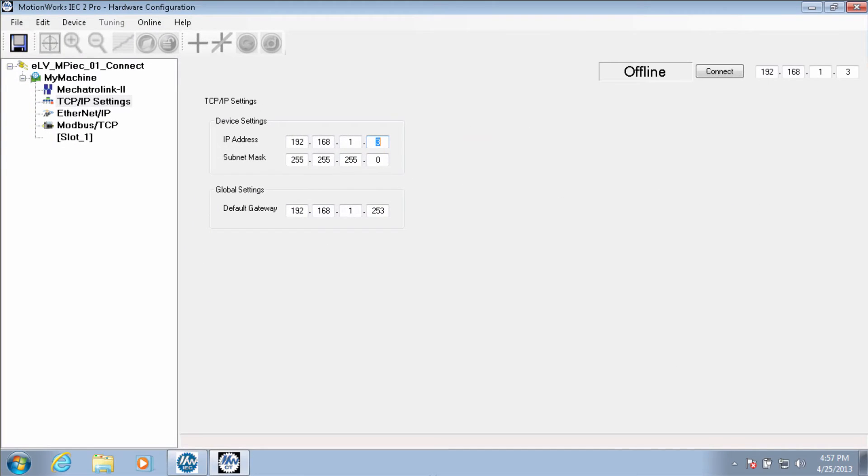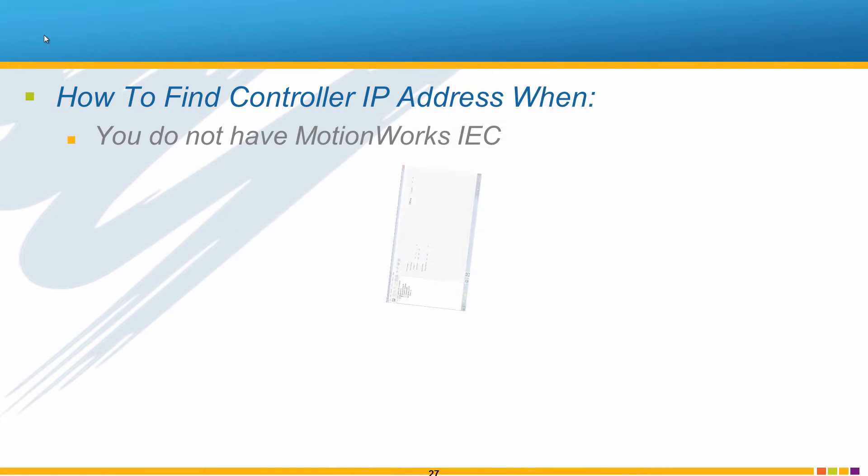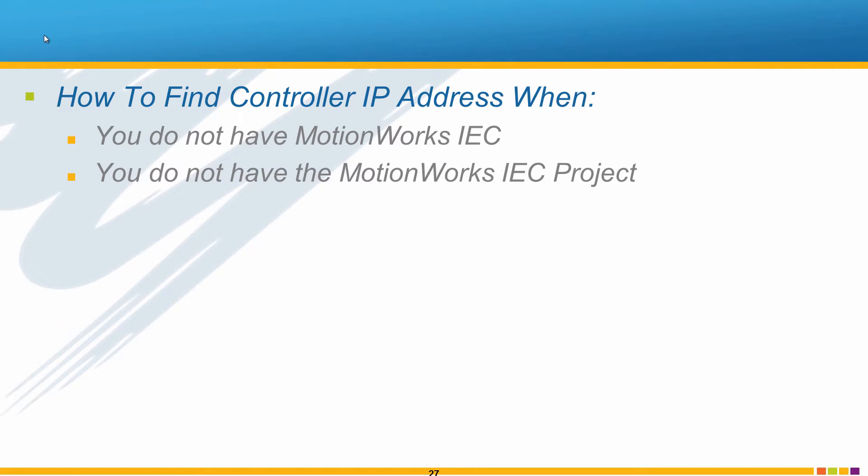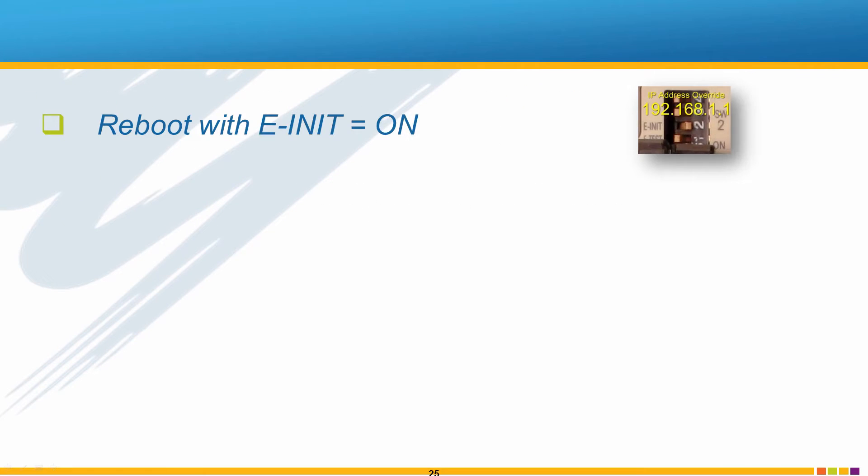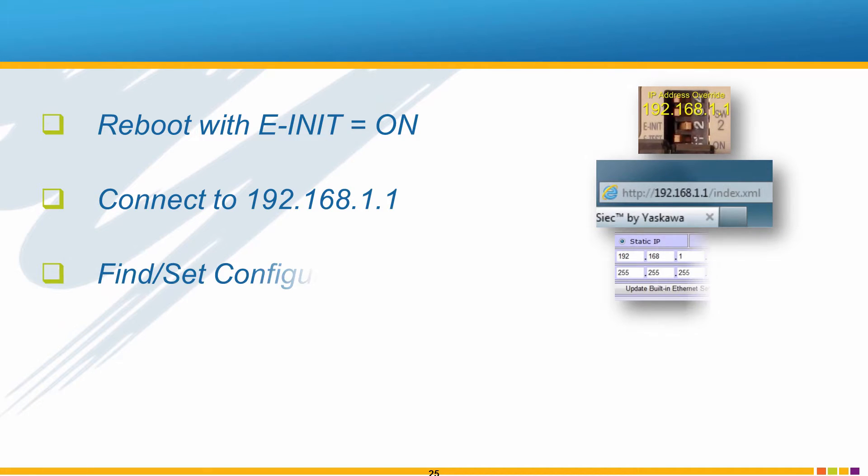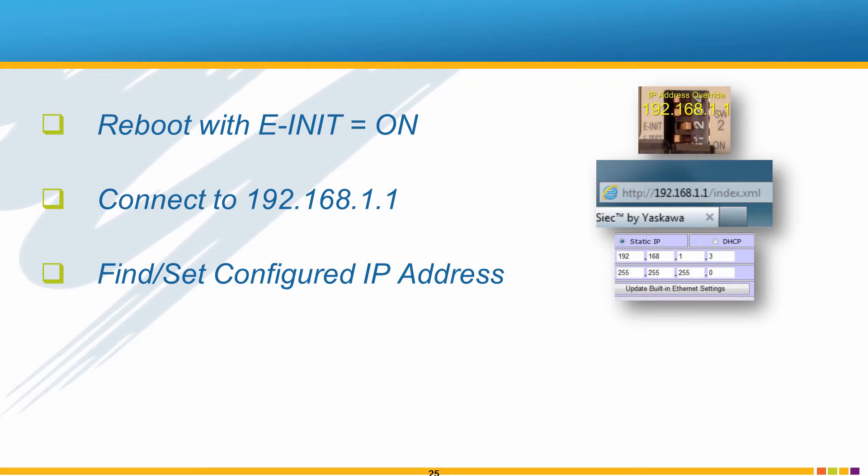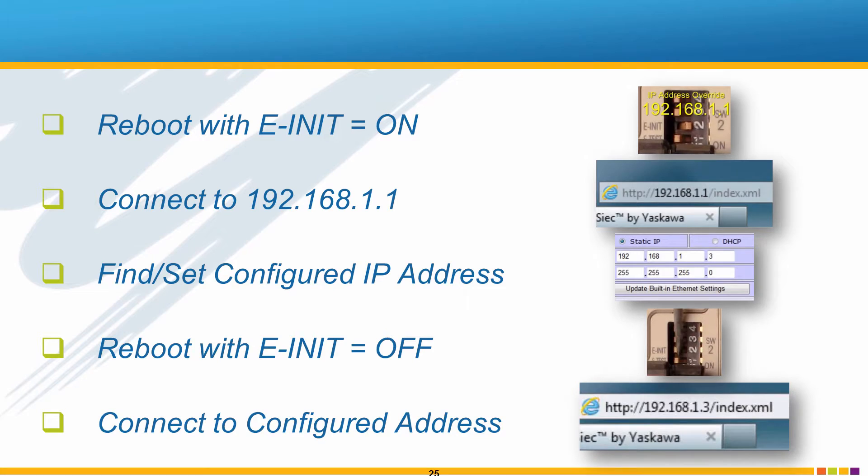However, if you don't have MotionWorks IEC, don't have the project, or just aren't sure if you have the correct project, then you can reboot the controller with EINIT on, connect using the override address, find the configured address in the web server, reboot again with EINIT off, and connect to the configured address.